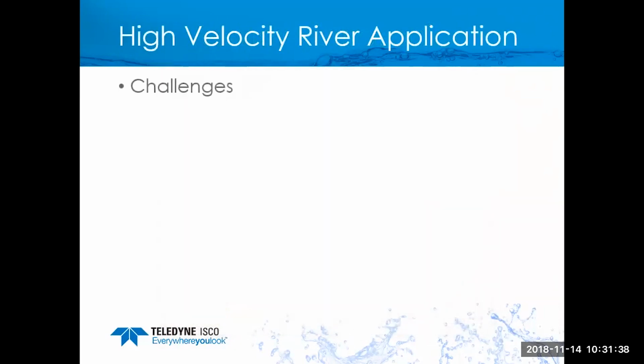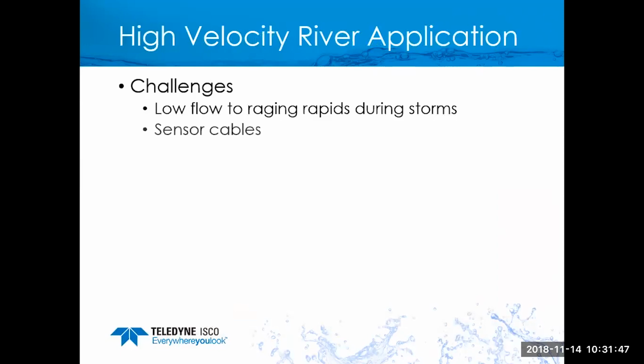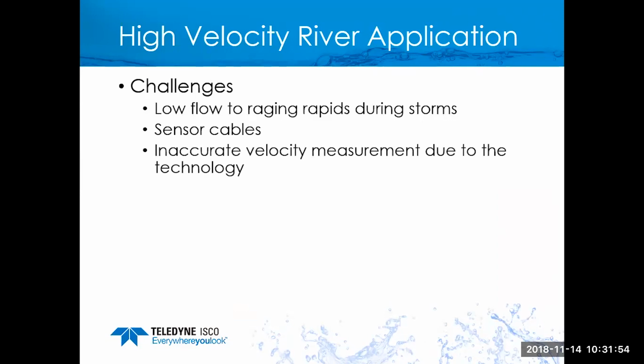Okay, river applications. We're seeing more and more of these. Typically, they're high velocity. They can go from very low flow or no flow to raging rapids during storm events. You have sensor cables that are in there in the traditional way, which are not good. The only way around that was to put in an ultrasonic to read level, but then you have level only, so you don't have a lot of accuracy there.